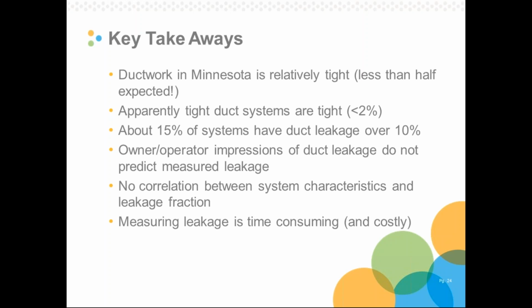And the last wonderful thing that we learned is that measuring leakage is time consuming. The actual static pressure test only takes a few minutes, but shutting down an air handler, blocking off inlets and outlets, and then doing the reverse of that to get the system online at the end takes a long time. It's at least a several-hour process per system.